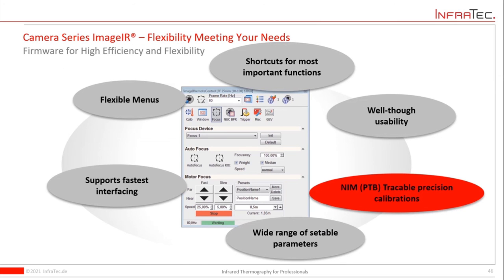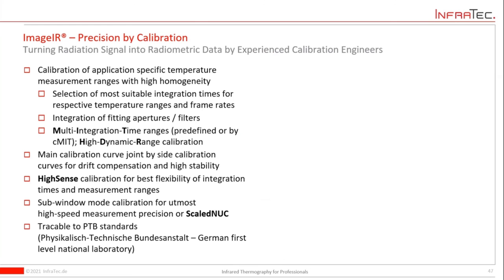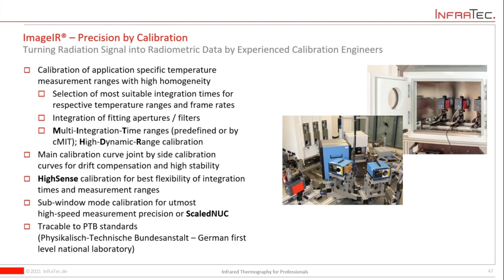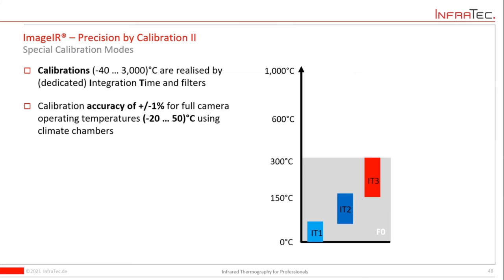I was already talking about calibration, and calibration is really a big topic for us here at InfraTec. Because it's a challenging topic, and that's why we take it on. Our calibrations, as I've already mentioned, are fully traceable to the German NIM. We can provide multi-integration time calibrations. We can, as I've already shown you, provide the high dynamic range calibration, but we also have other opportunities. Here you see standard ranges are always made in a way to accommodate the measurement needs of your application.